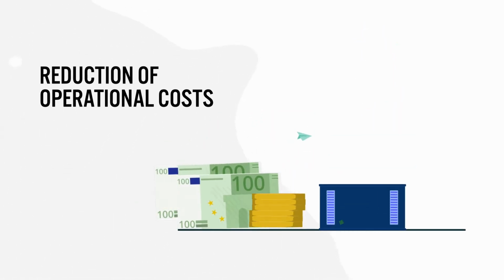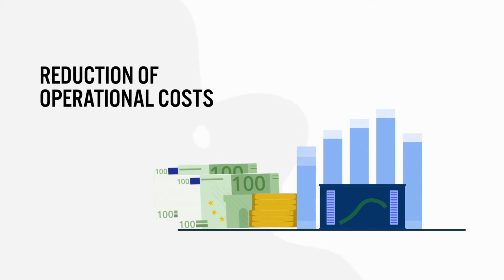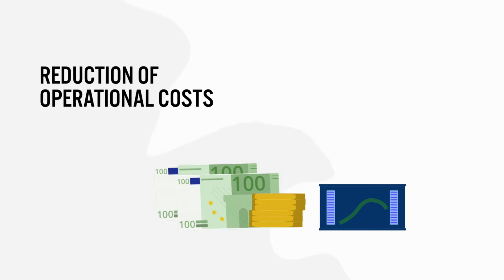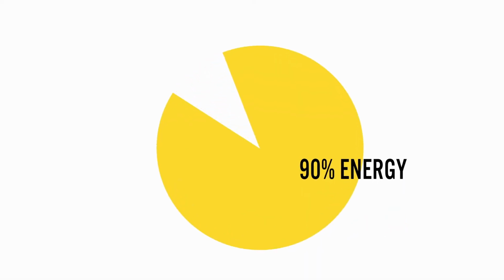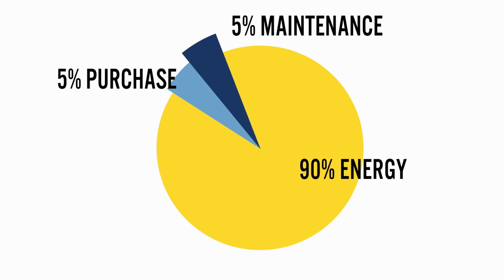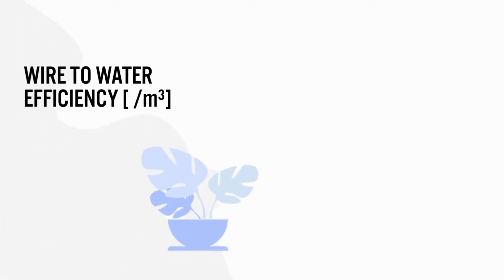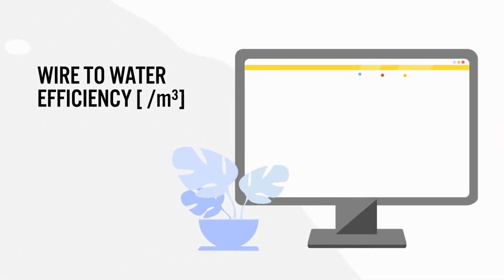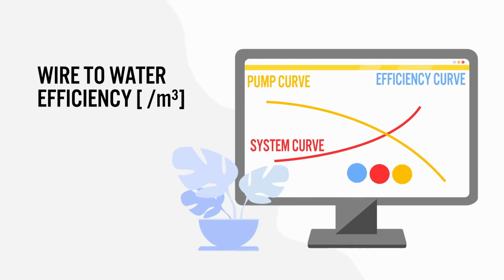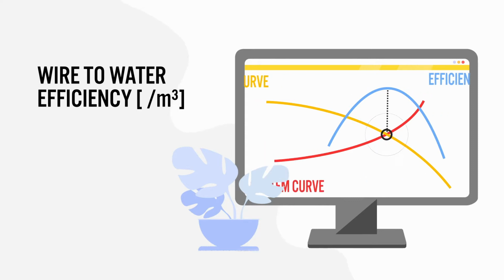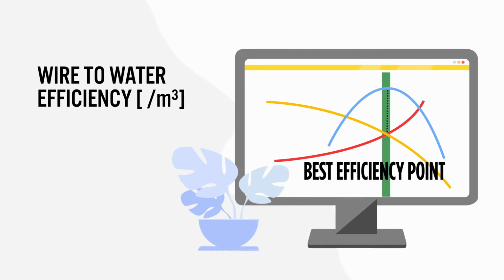When talking about cost, it's important to look at the total life cycle of a pumping system. Certainly, the capital investment for the purchase and installation are significant. Maintenance costs also play a role, but the biggest cost is clearly energy consumption, which accounts for nearly 90% of the life cycle cost. The so-called wire-to-water efficiency is the interaction of the system and the pump curves, which result in the ideal pump operating point, which should be targeted for the highest possible efficiency and configured with the right system components which match perfectly.